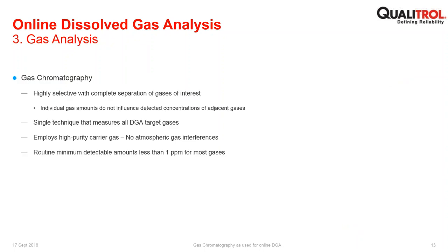So for gas analysis, I also mentioned that there are a number of different techniques: gas chromatography, solid-state sensors, infrared spectroscopy. But of course, we're here to talk about gas chromatography. Gas chromatography is highly selective with complete separation of the gases of interest. What this means is that individual gas amounts do not influence detected concentrations of adjacent gases. As you send the gas sample down through the GC column, each gas is physically separated from the adjacent gases, and what comes to the detector is a pure sample of the particular target gas. So there is no effect on the measurement of one gas from the measurement of adjacent gases.